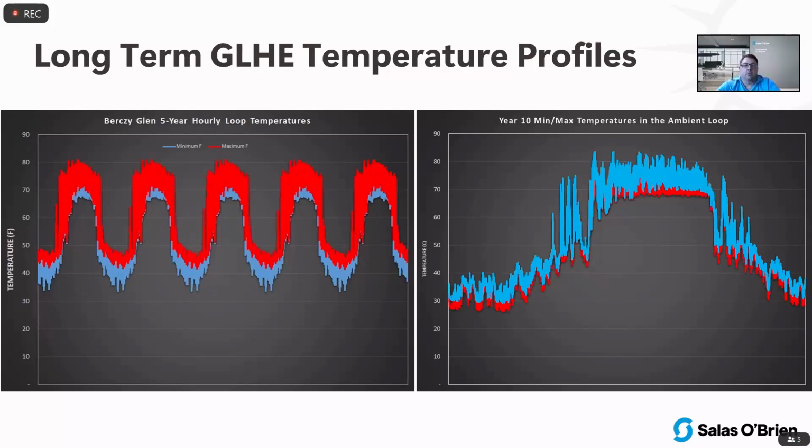So you can see here that you model 5 years, you model 10 years, even as much as 30, 40 years, just to see what the trend of that model looks like. And you can see here that there is no trend either going up or down, which means that we have a very stable and consistent load profile, both energy in, energy out. So the ground is going to be very stable over the long term.